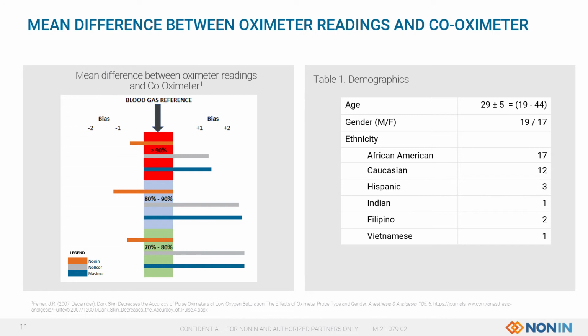And in this most challenging environment of low saturation, where the SaO2 is from 70 to 80%, and dark skin pigmentation, the bias for the Nonin PureSat oximetry with clip sensor was minimal at negative 0.6%. This is in contrast to the competitors' clip sensor results, with a mean bias of 2.61% and 2.59% in the same subgroup. And in this study, Nonin readings biased slightly below the blood gas reference, which may ensure greater patient safety, as higher readings may run the risk of failing to identify patient status that could represent a clinical concern.